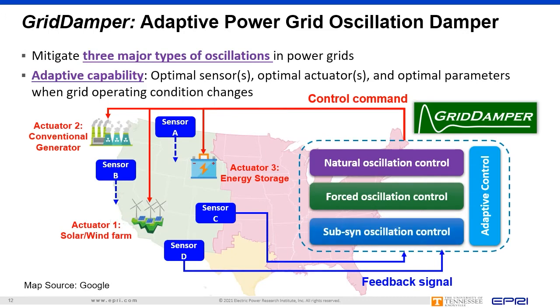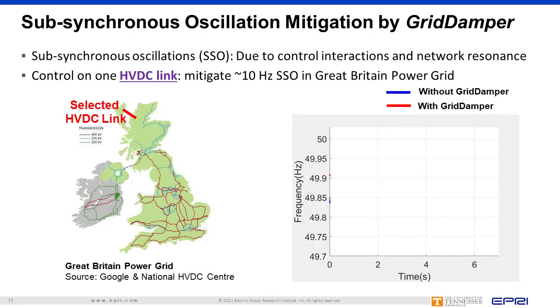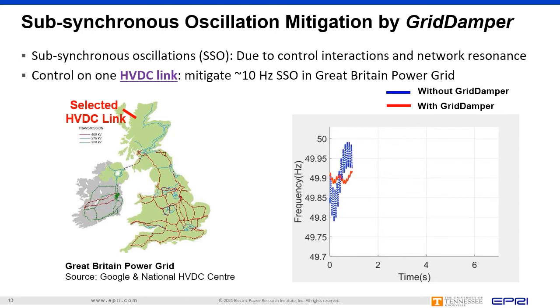In the United Kingdom, sub-synchronous oscillations may happen in the power transmission network due to interactions between renewables, HVDC, and the power grid. As an example, an artificial 10 Hz sub-synchronous oscillation was created in a simulation model representing the UK grid after 2030. Grid Damper was able to detect this 10 Hz sub-synchronous oscillation and quickly deployed control on the high-voltage DC link in the north to settle the high-frequency oscillations.